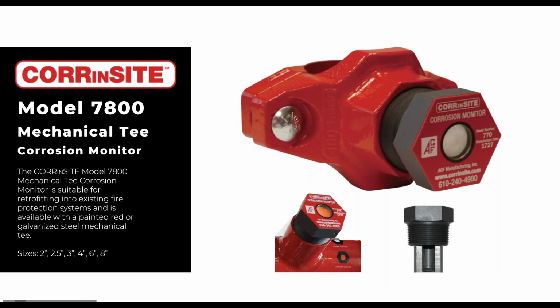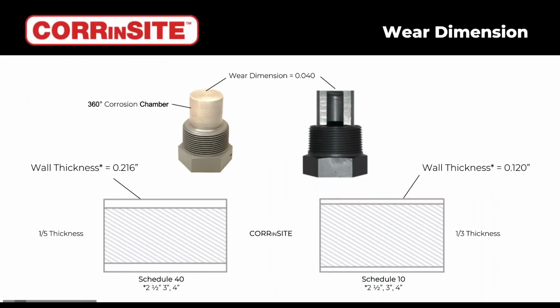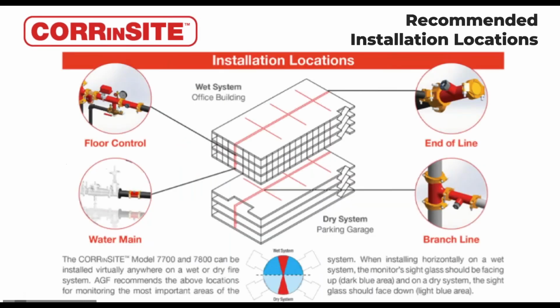So we make it for both new and retrofit construction, offering it both as a pipe spool as well as for application onto a mechanical tee. But how the unit works is it's a hollow chamber. The end of the unit, which is down in the system, is machined down to be 1/3 the thickness of Schedule 10 pipe. So if there's any type of corrosion event, and air or water comes into that chamber, it changes the sight glass on the outside of the pipe to bright orange.